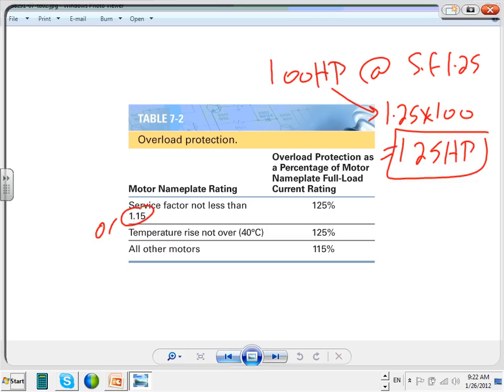But say I'm running it 24 hours, right? And within that 24 hours, most of the time I need 100 horsepower. But at certain times I need to pull 125 horsepower out of it. I'm going to dare say 20 minutes. There's 20 minutes when things jam up, rush hour, and we're overloading it. A 1.25 service factor will be able to handle it. But a 100 horsepower motor with a service factor of 1 will trip. It will trip on you.